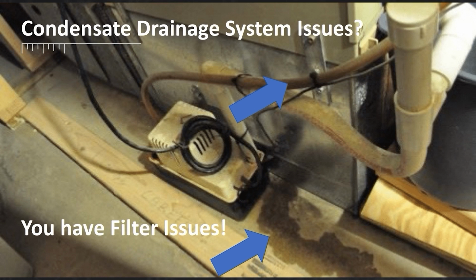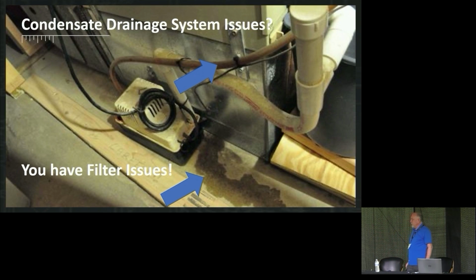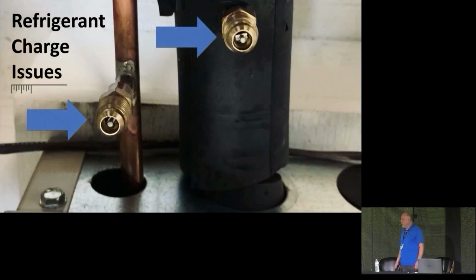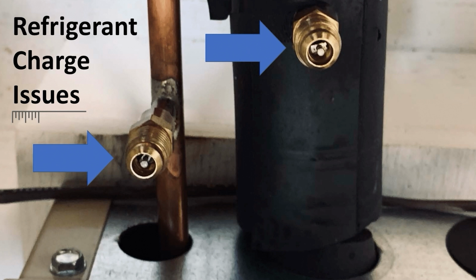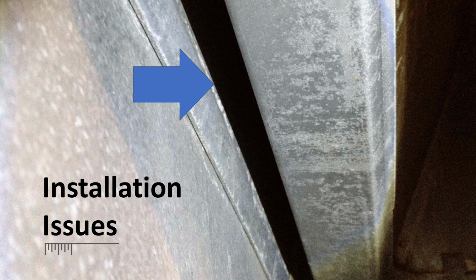This is also, we want to watch for rust. That's a pretty good indicator. When you're walking outside, you see rust coming out. This was full of rust on here. This one's not only a filter issue, but it's also an evaporator pan that's rotting out. Refrigerant charge issues, pretty self-explanatory. Caps left off. Installation issues, this is the bottom of an evaporator coil where it has no pan. Air's blowing by the evaporator coil. MeasureQuick will pick that one up also, right?